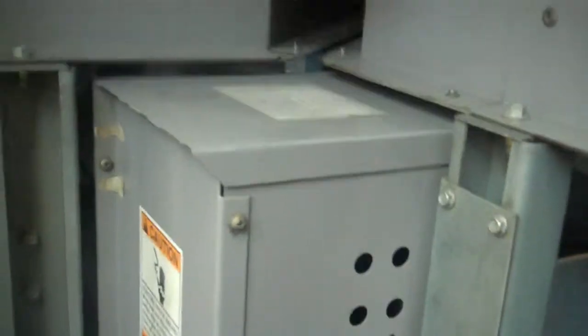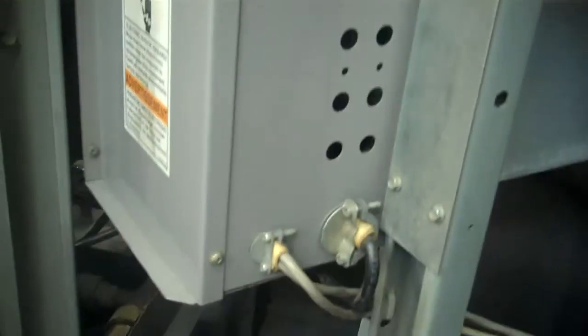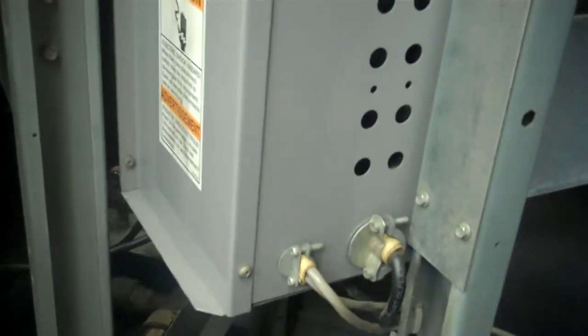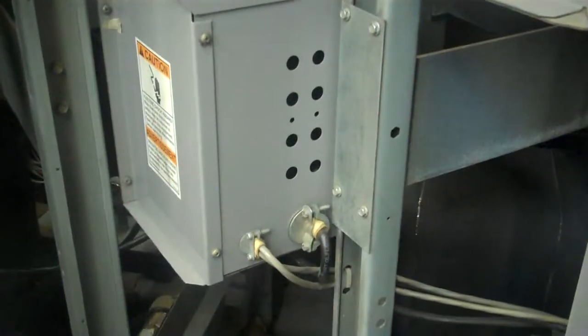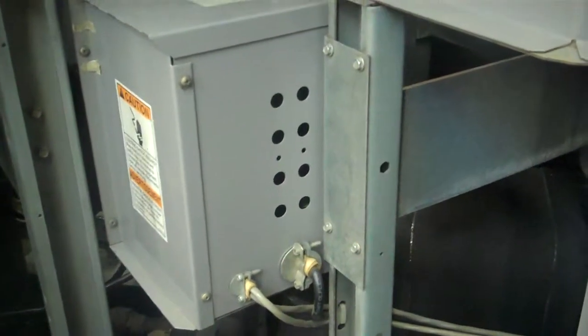Takes 2-inch process piping. Behind this enclosure here, this is the low ambient option, which is a Motor Master variable speed drive. That allows for year-round process cooling if the chiller is located outdoors in a cooler environment. You can see here that rectangular insulated thing, that's the braze plate exchanger. And here is the expansion tank for the hydronic option. If you do want to run a pressurized loop, that expansion tank is going to help you out.